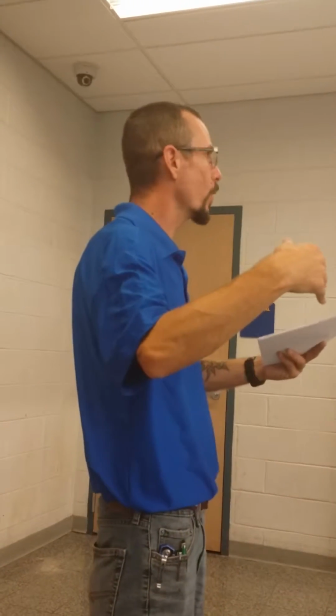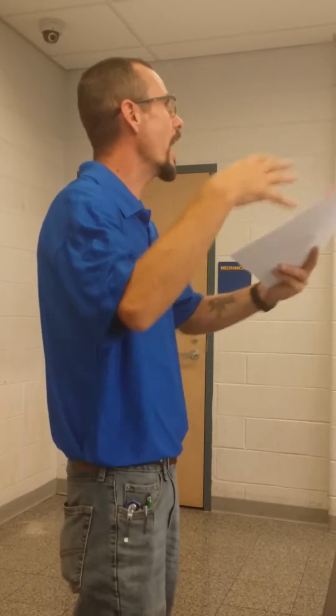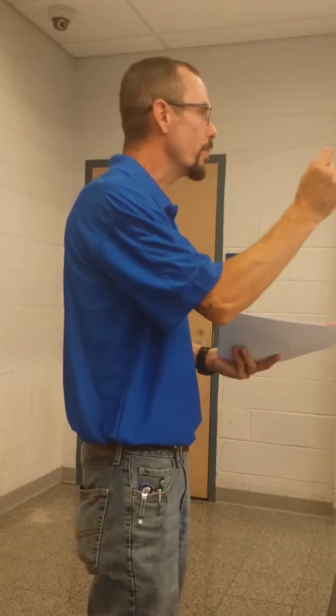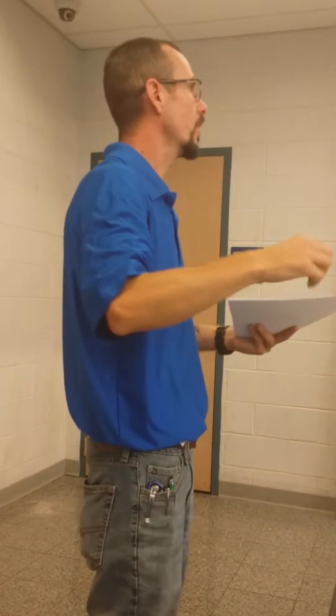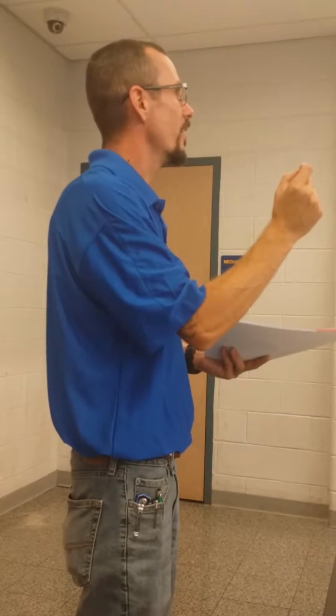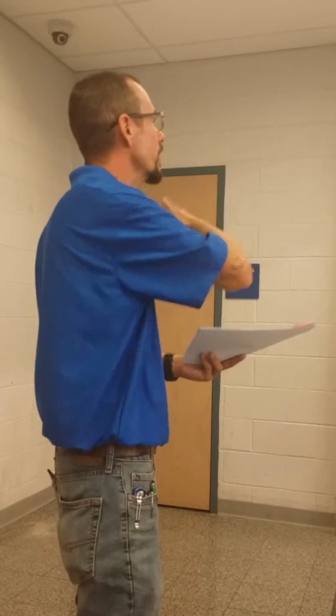You already had the blower out. Let's clean the guy while it's out. Clean the housing, clean everything around it. It doesn't just preserve the life of the motor or the bearing within, it provides cleaner air. That dirt buildup, we have moist air going all around us, even though we're trying to control humidity in this building, it turns into a muddy substance. That muddy substance turns into mold. You are now projecting that mold every time that unit comes on. This is an unsafe, unclean environment for the kids, for you, for the teachers, for everyone that's around. So again, RTFM, read the freaking manual.